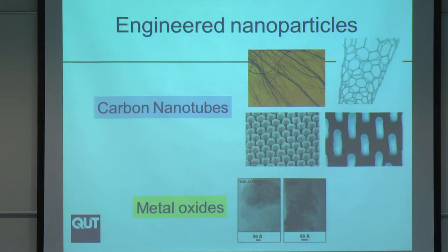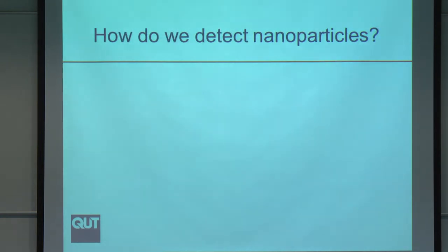Now if you think about devices like SMPS, CPCs, and so on, they always express what's happening to these particles, or they assess these particles, based on their sphericity. This is not spherical. So this is another factor which, if you really want to get deeply into the science of what the instruments measure, you need to consider aspects like this. So, how do we detect nanoparticles?